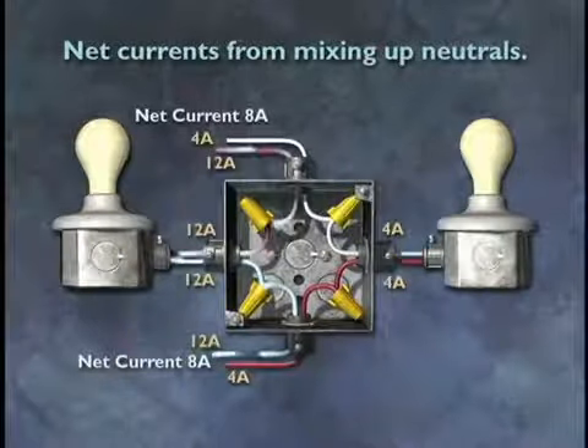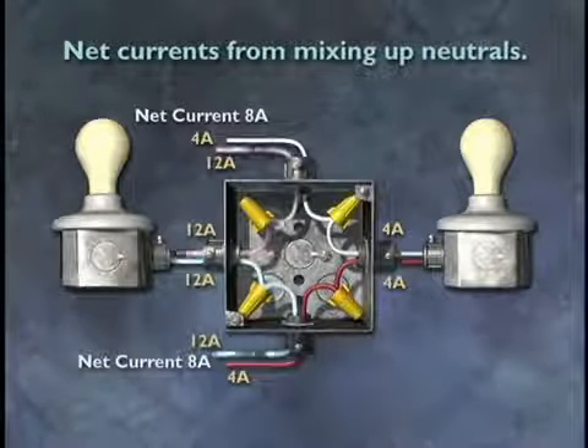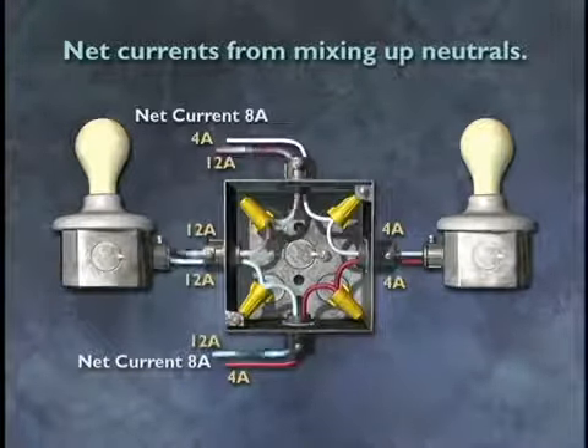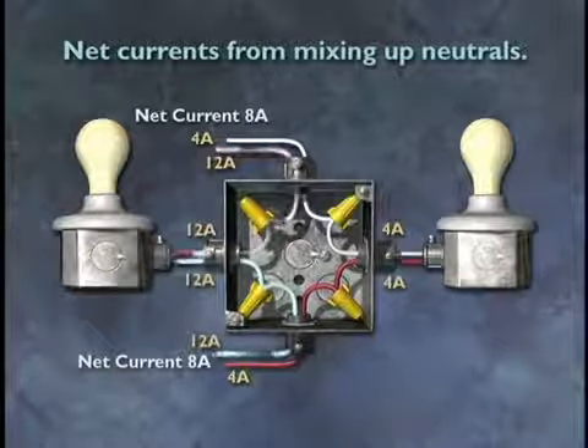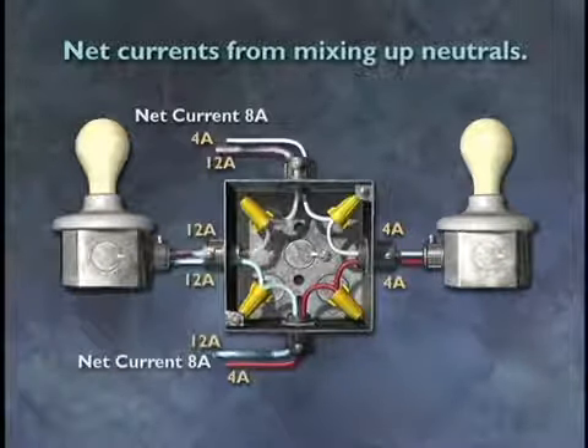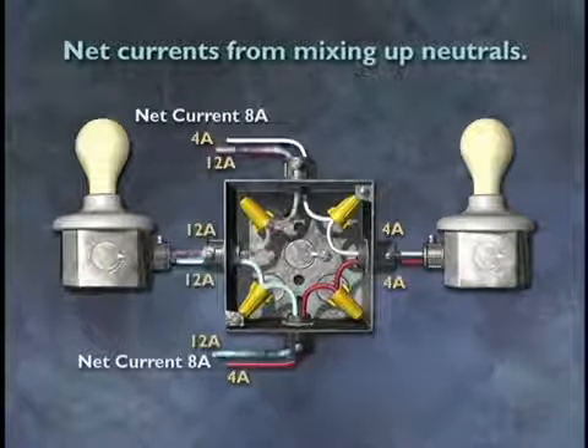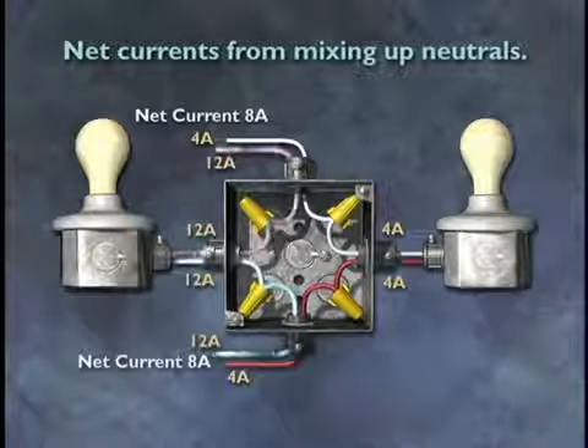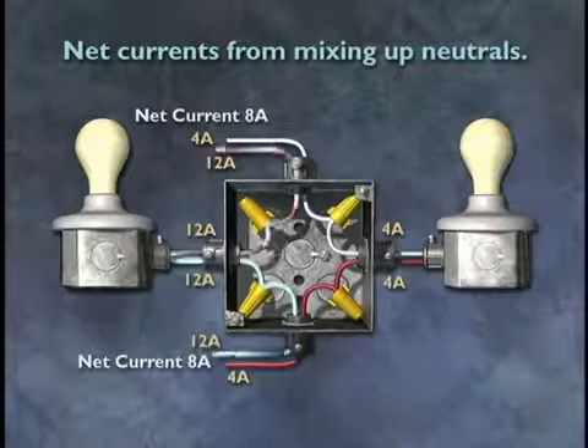In this example, the neutrals are mixed up. When the wrong neutrals run with the circuit, there will be net currents. The installer did not pay attention to which neutrals he was connecting, but since the lights came on, no one noticed. And in a situation where one hot leg has been paired with a neutral of the other hot leg, the result is that instead of subtracting from the hot, the neutral will add to the hot, producing a high net current.